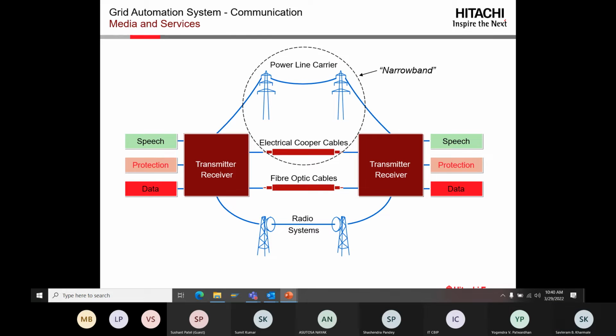What are the communication media generally used in the substation environment? A transmitter and receiver is always required to make communication, along with a media to transmit speech, protection, or any kind of data. Here we see radio system at the bottom. Earlier radio systems used microwave links, but nowadays this has been replaced with fiber optic communication, and in some cases electrical copper wire or power line carrier communication is used. That radio frequency band has now been freed up and given for 4G or 5G communication, so radio systems are no longer used in substation environments.